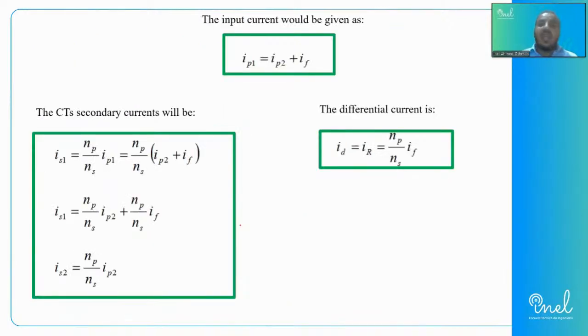Based on those formulas, at the end we have a certain formula which confirms how we can relate the current at the primary side and the current at the secondary side at a fault moment, especially if there is a turns ratio, which confirms there is a proportional ratio between secondary and primary side, as we were referring to in the transformer explanation. While we were explaining and digging into the details of the transformer, we found such proportionality based on the turns ratio between secondary and primary. But in case there's a fault, the differential current would exist, and a tripping action can be created by the relay, or differential relay.